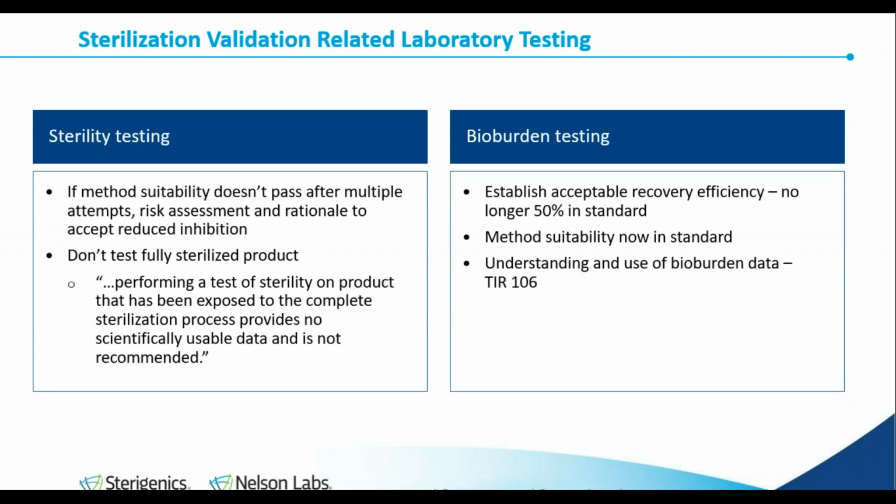Also, we added a couple of bits of guidance here, and this goes back to the performing of sterility testing on fully sterilized product. So in the introduction, for example, we added this sentence here that performing a test of sterility on product that has been exposed to the complete sterilization process provides no scientifically usable data and is not recommended. And I'm going to talk about this a little bit more on the next slide, so I won't hit on that too much more right now.